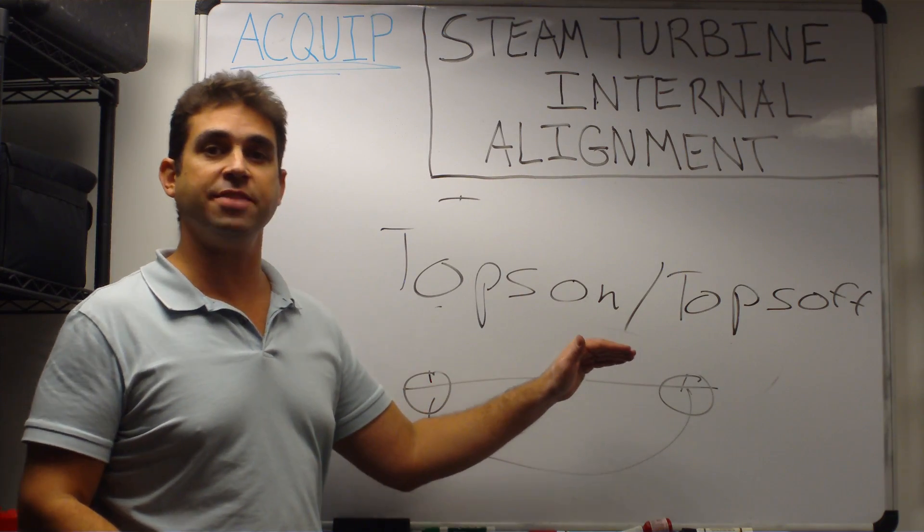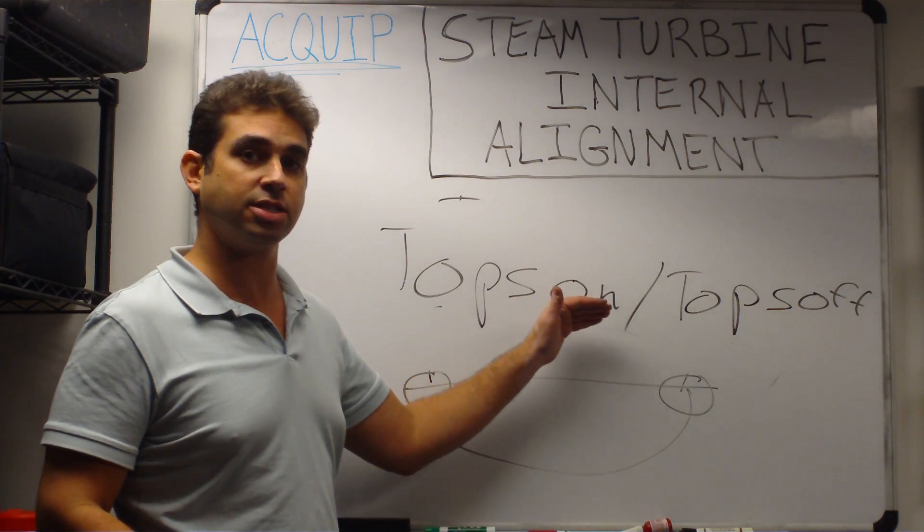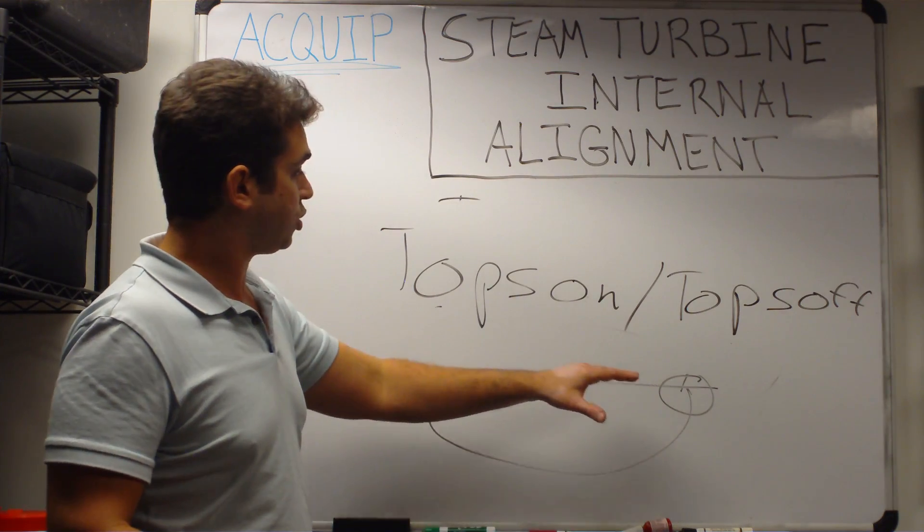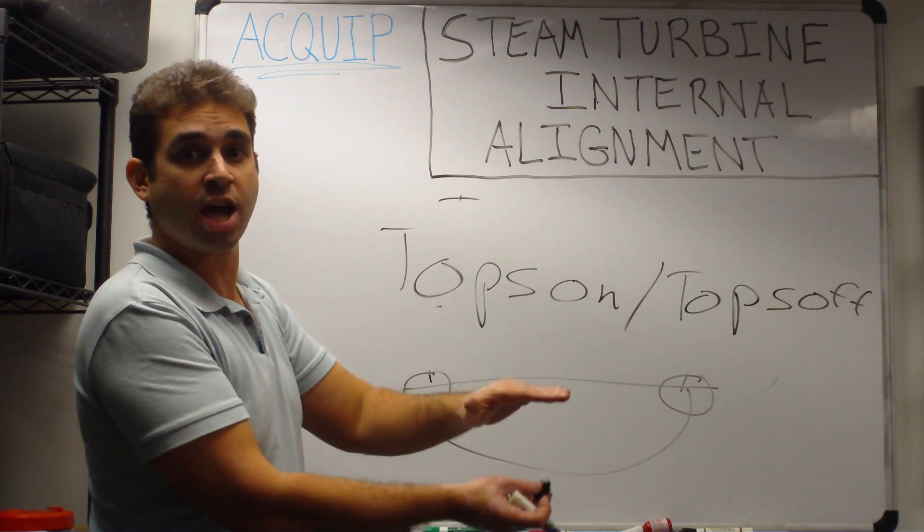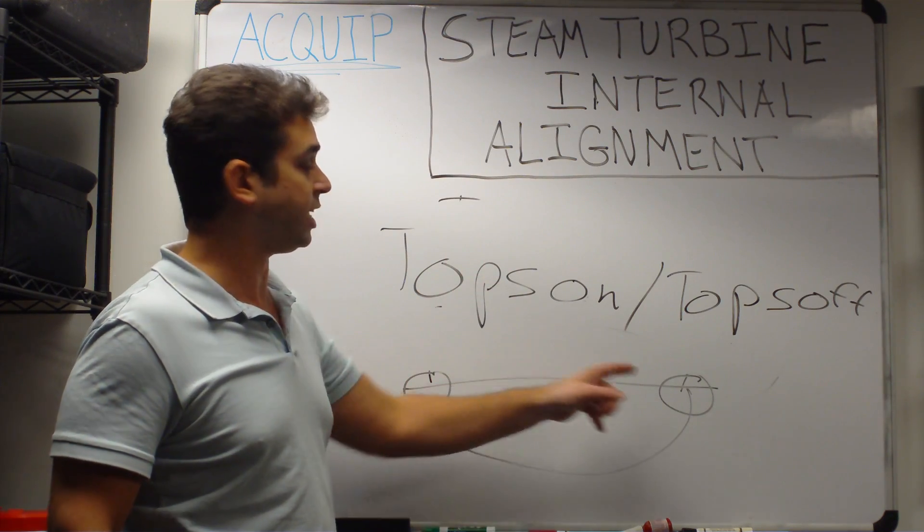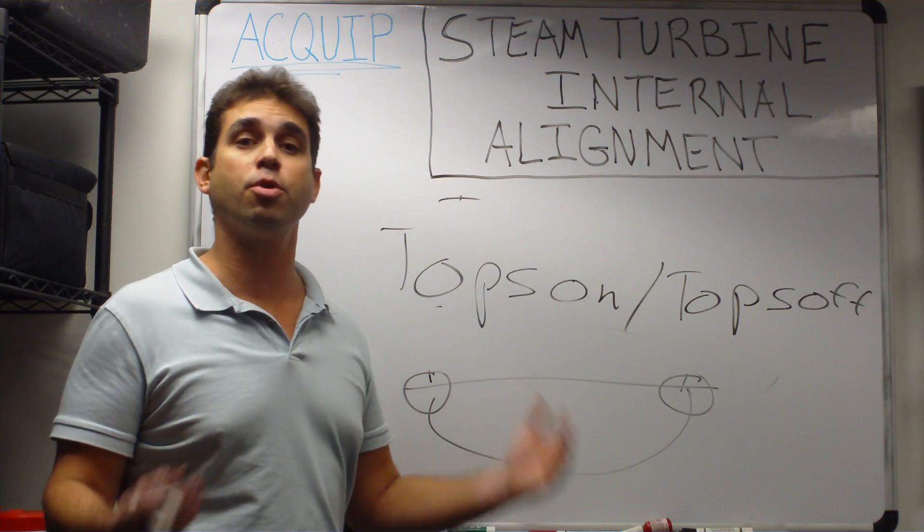We calculate the deviation from the tops on readings to the tops off readings so that we know what that change is when the top goes on to the top being off. We take all of our readings to do all of our moves with the top off the turbine.